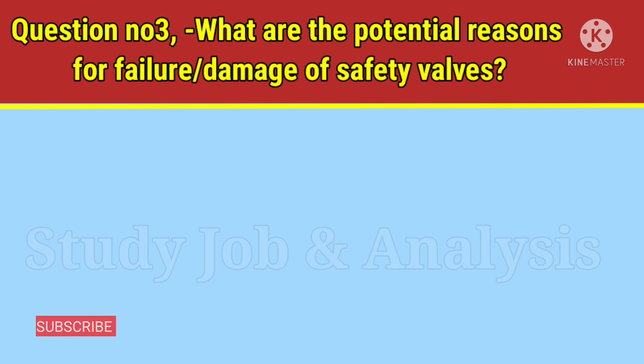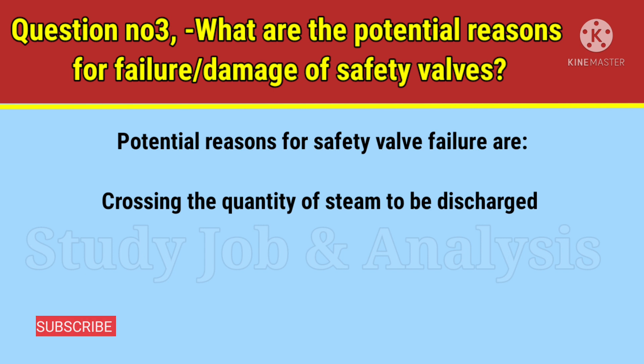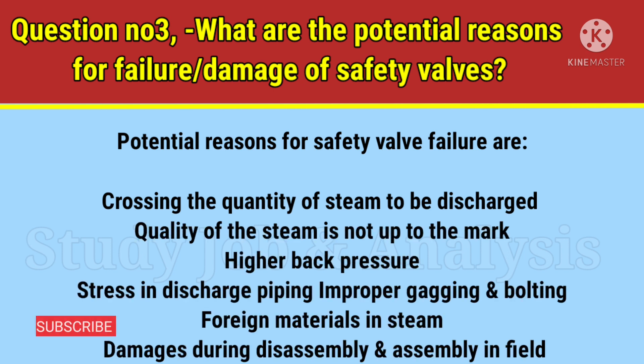Question number three: what are the potential reasons for failure or damage of safety valves? Answer: Potential reasons for safety valve failure are — exceeding the quantity of steam to be discharged, quality of steam not up to the mark, higher back pressure, stress in discharge piping, improper gagging and bolting, foreign materials in steam, and damages during disassembly and assembly in the field.